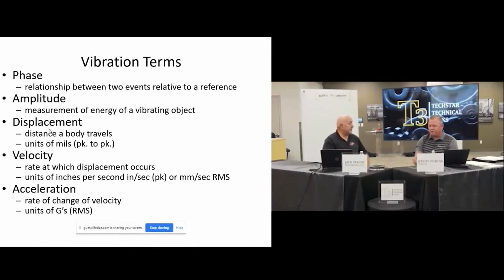And a lot of times there's cost considerations of drilling and tapping and installing these sensors, running additional wiring, things like that. So it's not really cost effective to put a sensor in each individual plane. In those cases where you can't justify the cost of doing that, a triaxial sensor gives you data that's good enough to work with. Absolutely. That's good enough.